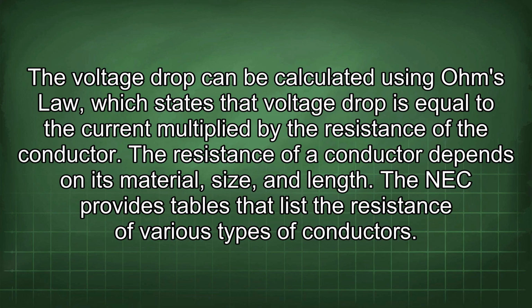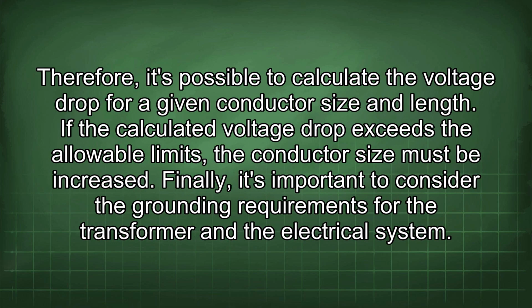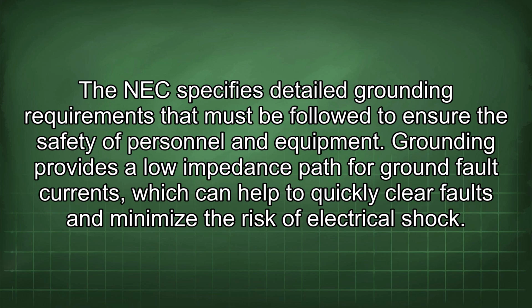The resistance of a conductor depends on its material, size, and length. The NEC provides tables that list the resistance of various types of conductors. Therefore, it's possible to calculate the voltage drop for a given conductor size and length. If the calculated voltage drop exceeds the allowable limits, the conductor size must be increased. Finally, it's important to consider the grounding requirements for the transformer and the electrical system. The NEC specifies detailed grounding requirements that must be followed to ensure the safety of personnel and equipment.